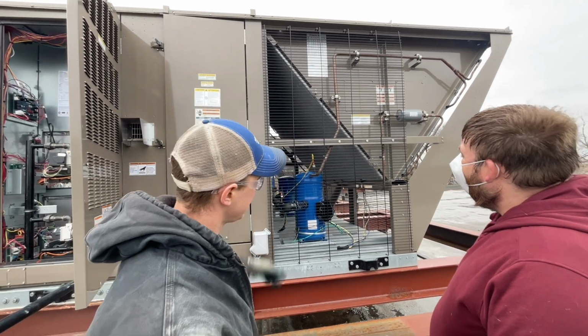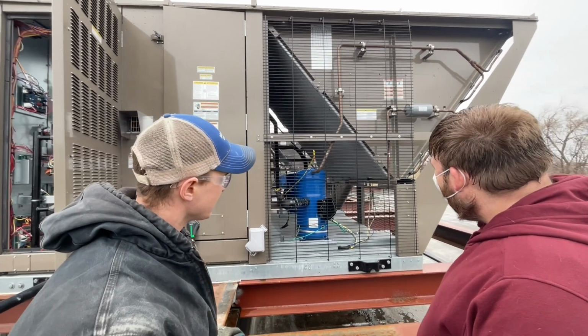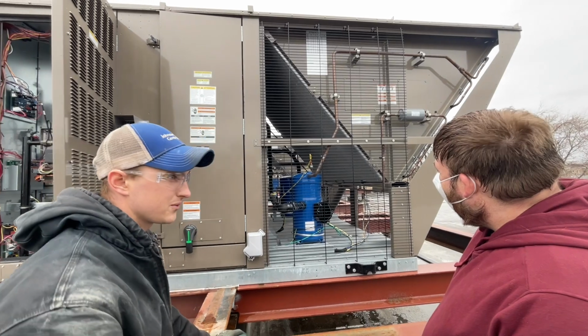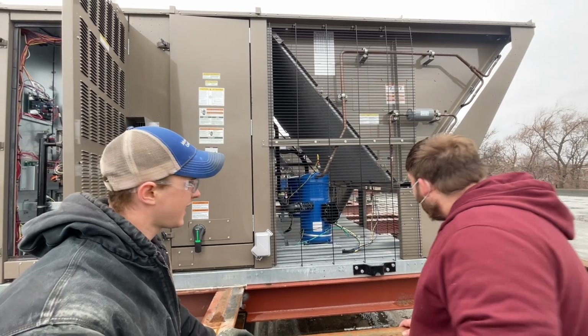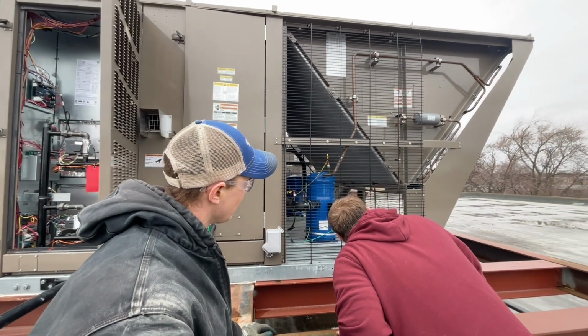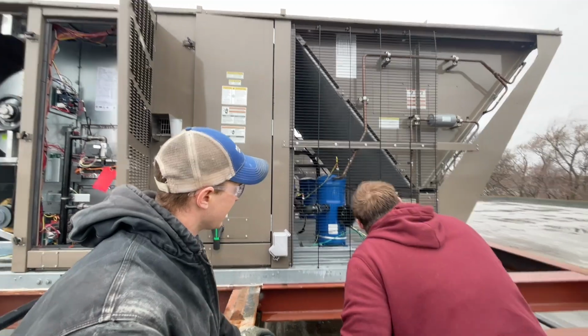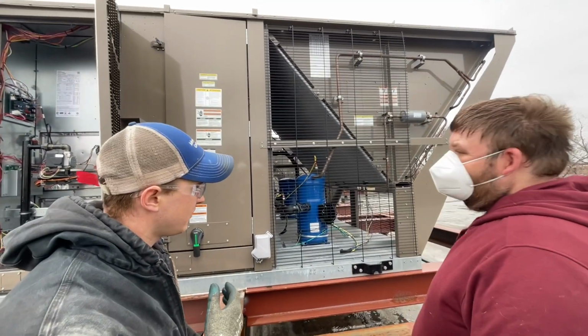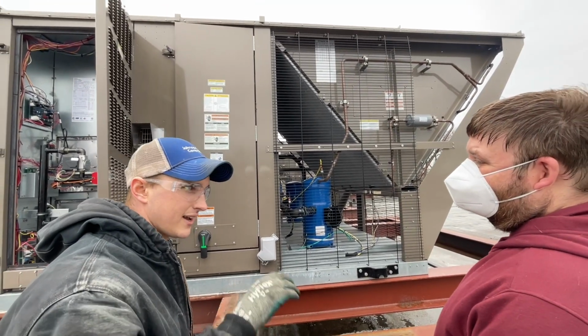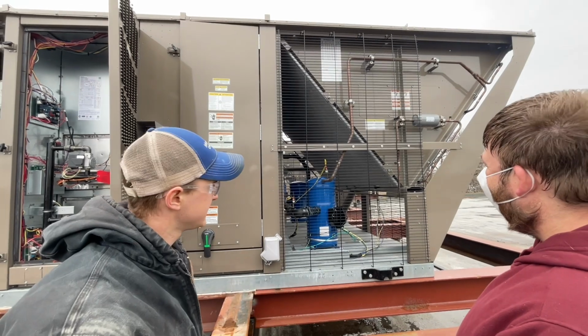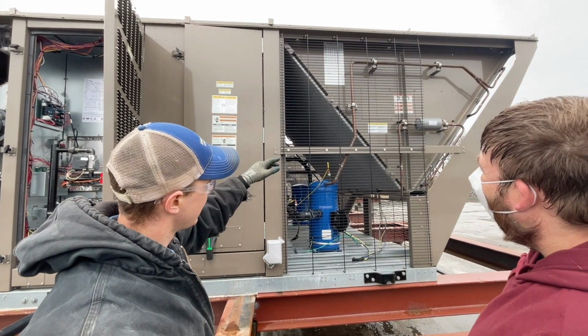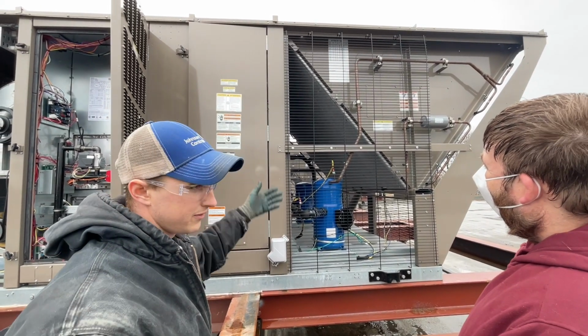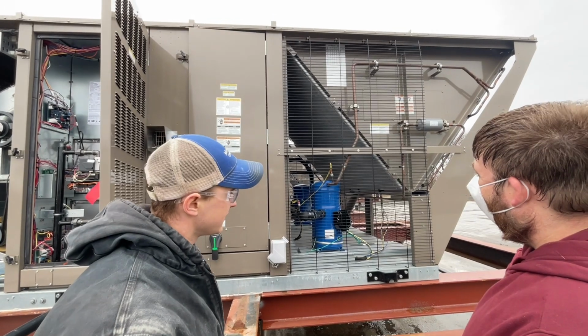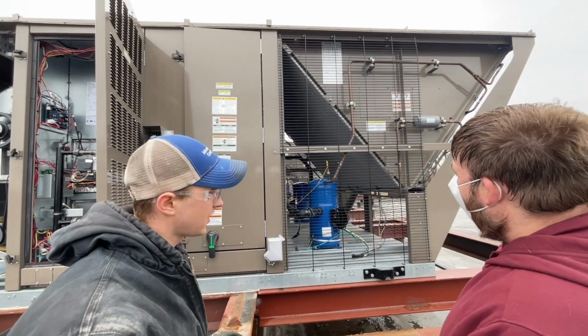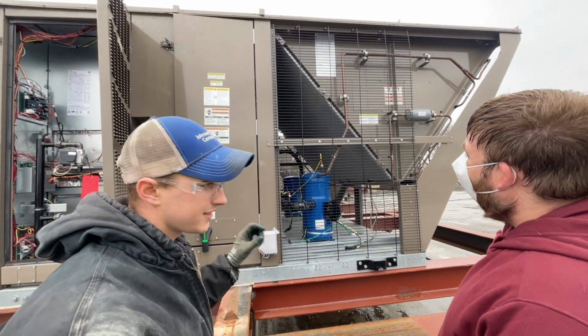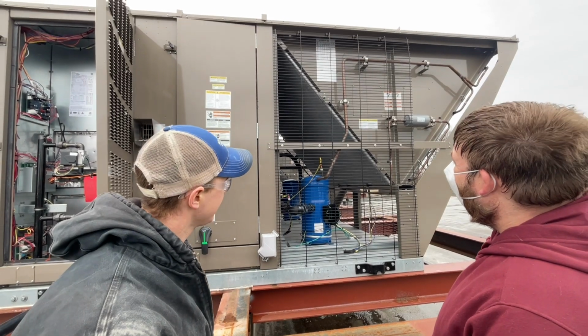Second thing, in addition to the filters and belts, what you're going to do most is clean the coils. So these are micro channel coils. I don't know if you ever had to deal with these. They're more like a car radiator, not like the old ones that have a copper tube with aluminum fins. These are micro channel, so they're way more efficient, which is why they do it, but they're definitely more fragile. It's all aluminum, pretty thin aluminum, to get that efficiency out of it.